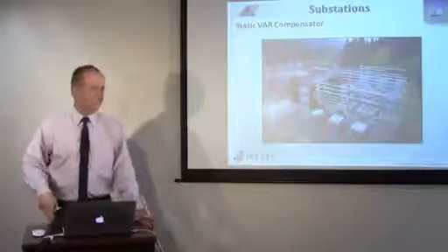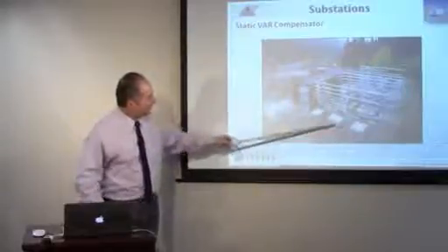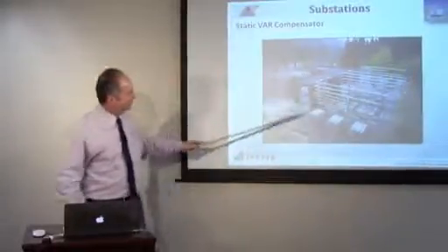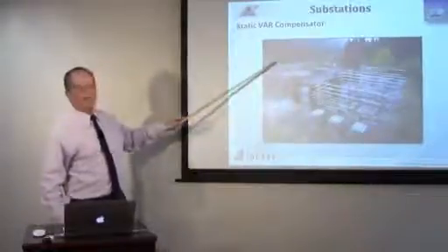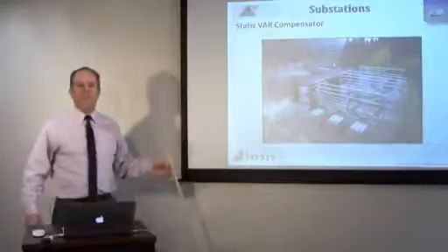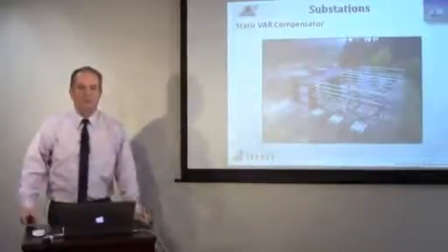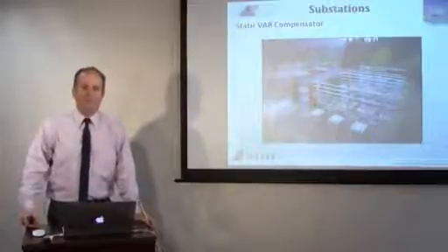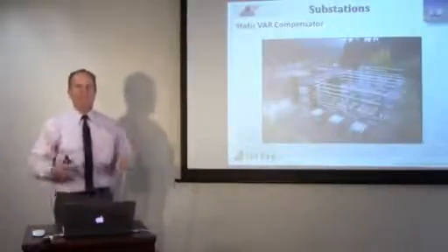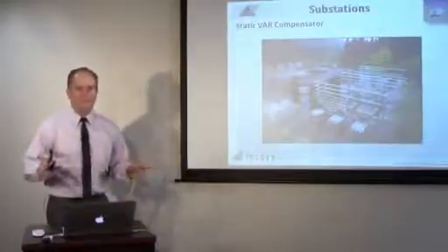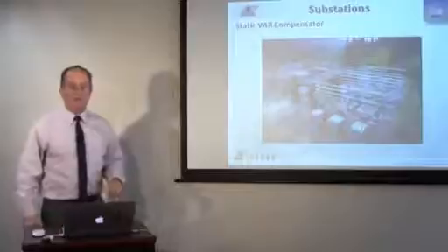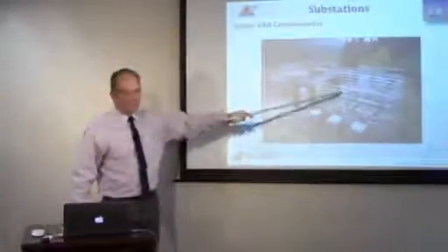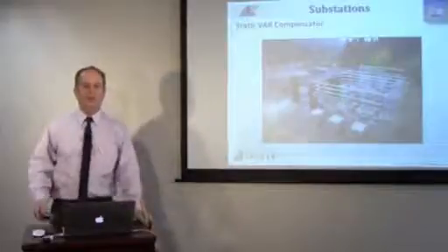Okay, now, this is a picture of a static VAR compensator. This is a device, equipment that is used to house both reactors and capacitors. If you look here, we've got capacitors and we have reactors. And between the two, you can control the VAR flow on the transmission line. So it's actually compensating for the reactance and capacitance of a long transmission line to make the line electrically shorter, to be more stable, to improve system reliability and those types of things. A static VAR compensator is a combination of capacitors and inductors to help the electrical characteristics of the power system.